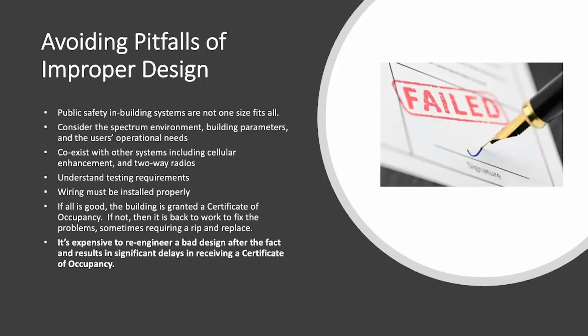As you can see, there are very specific codes which must be followed. It's very important that the engineer designing an ERRCS system communicate with the AHJ to ensure that the final system will satisfy their requirements upon completion. Requirements may not be the same as they were in the last project. If a first responder agency is planning to upgrade their radio system to a newer technology or to change their dispatch operations, it's very important to take those plans into consideration to make sure that the commissioning tests are successful and that the AHJ grants approval in a timely manner.